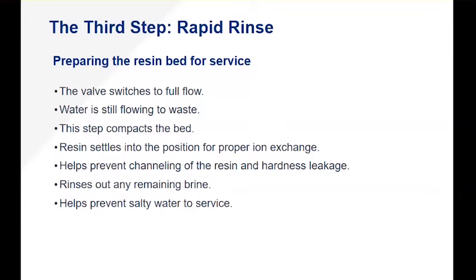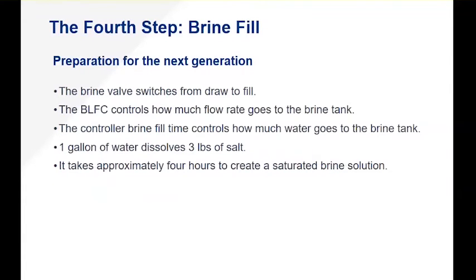Once we've rapid rinsed — and this is where you can save a little bit of time and water during your setup process — as long as you get enough time to rinse it clean and you don't have any issues, you can shorten this cycle to save a little bit of water. The fourth step, typically, is brine fill. We're now going to take some of that incoming tap water, and the brine valve is going to switch from draw to fill. The brine line flow control — a little rubber gasket with a hole in it inside the tube that goes down to the brine tank — controls the rate at which the brine tank fills.